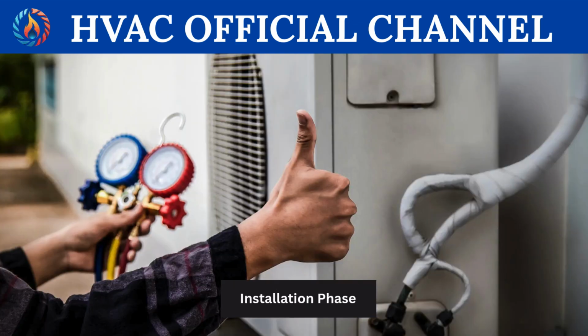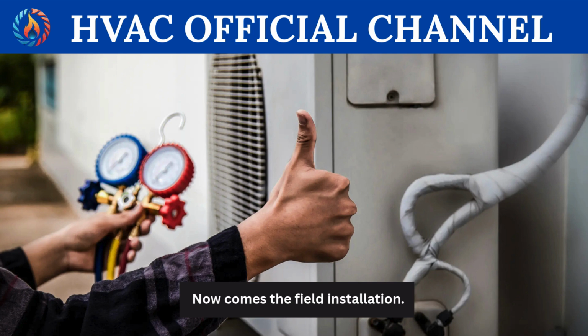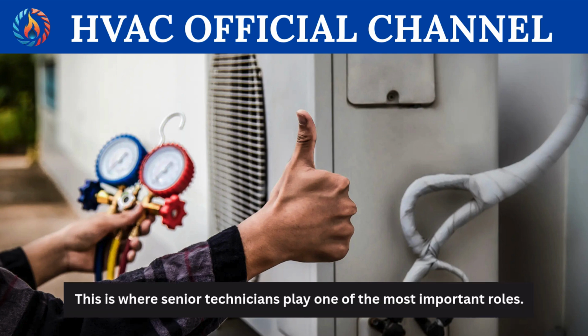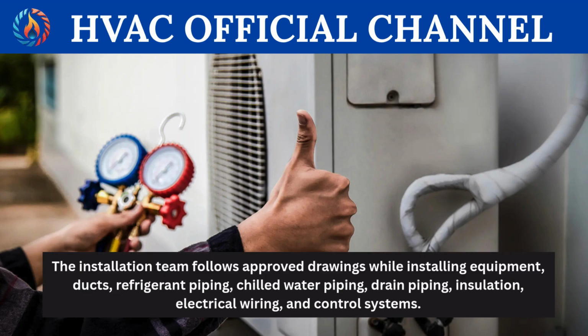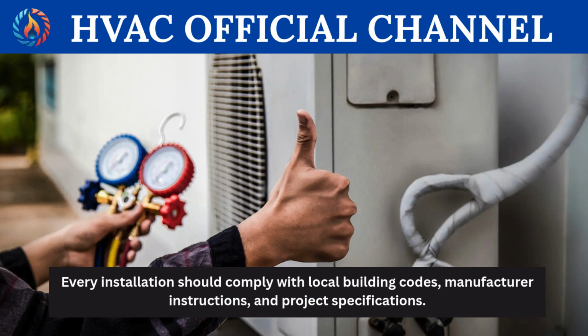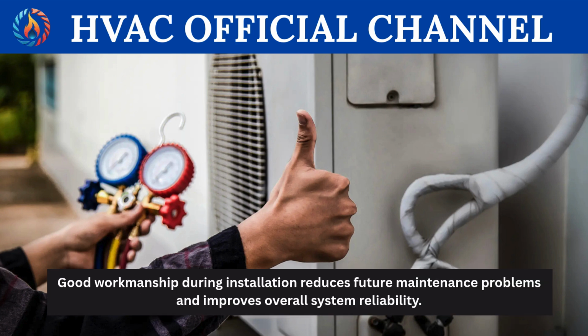Installation phase. Now comes the field installation. This is where senior technicians play one of the most important roles. The installation team follows approved drawings while installing equipment, ducts, refrigerant piping, chilled water piping, drain piping, insulation, electrical wiring, and control systems. Every installation should comply with local building codes, manufacturer instructions, and project specifications. Good workmanship during installation reduces future maintenance problems and improves overall system reliability.